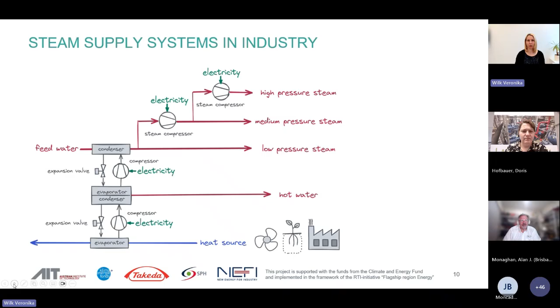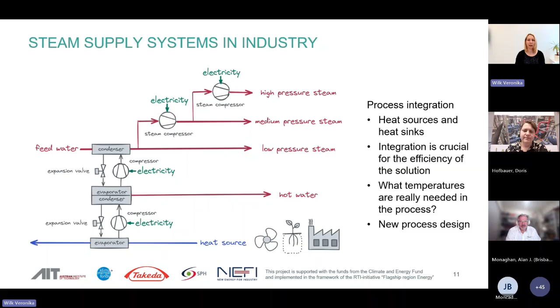When implementing these systems, it's important to think about the actual needs of the process—what temperatures are really needed, not necessarily maintaining the supply temperature level as in the past. Integration is crucial for efficiency, because the electricity consumption of a heat pump depends on the temperature lift, the difference between the heat source and the heat sink. The lower the temperatures, the more efficient the process becomes.